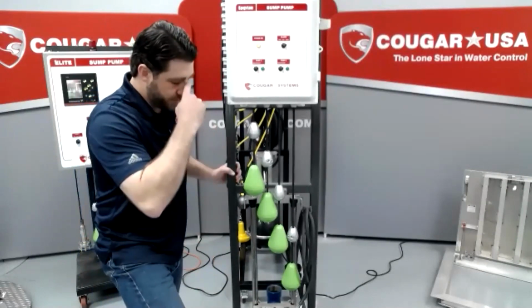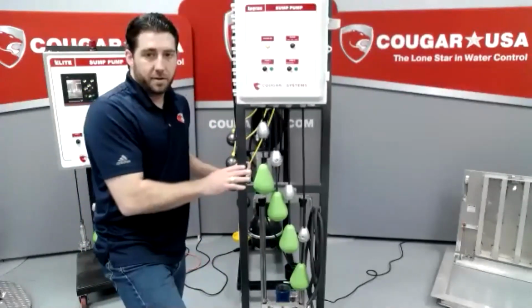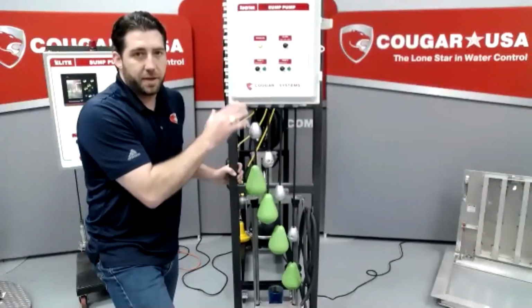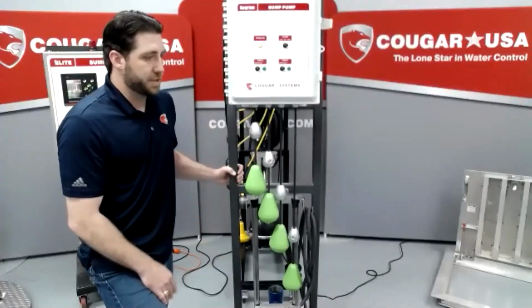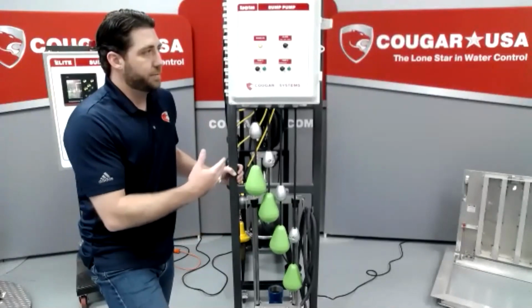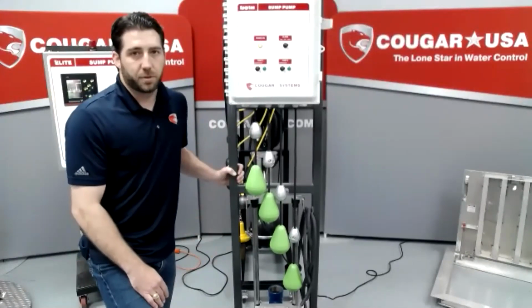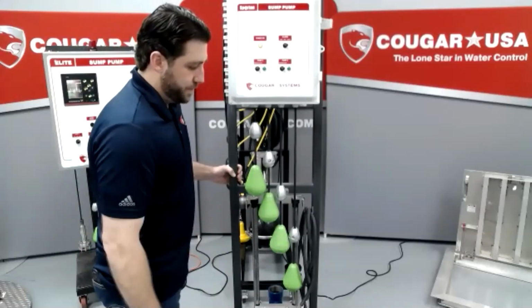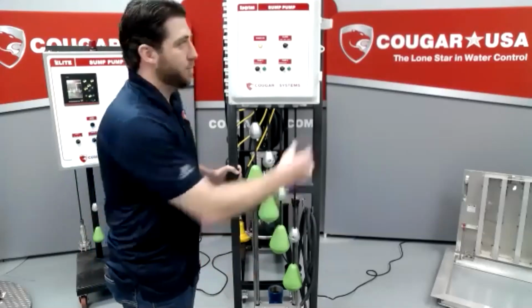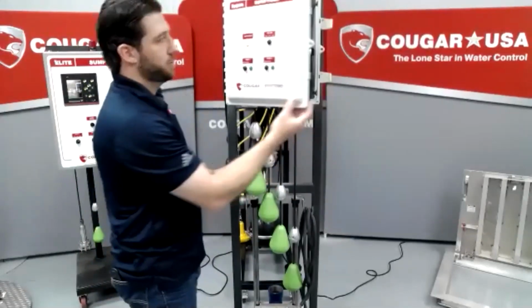So that's really what I wanted to point out here, is that anytime we have a relay logic style panel with the float switch assemblies, that bottom float switch is very important. And we don't have any way to really mitigate that bottom float switch not working. We can address that with some of the other panels.